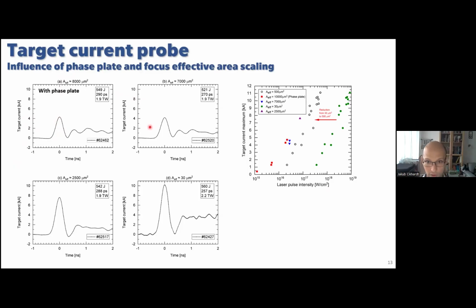This shot is with a very similar effective area, so we defocused the focus and we didn't use the phase plate. All the other conditions are the same. Very similar energy, very similar pulse duration, and practically the same power. And the result is that the target current is practically the same. All the waveform is the same.